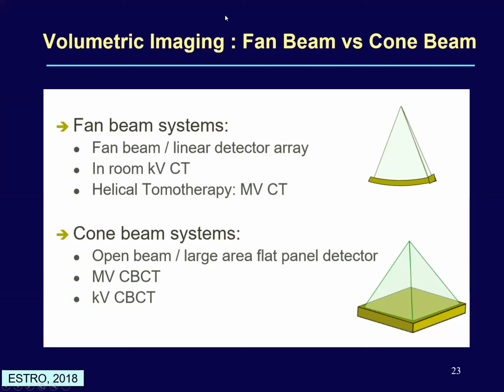Now coming to volumetric imaging, fan beam versus cone beam. What is fan beam? A single KV source with a linear array detector on the O-ring, and the source rotates in a helical fashion, and you can have a fan beam CT, which is conventionally available in all diagnostic CT scanners. In the same way, in helical tomotherapy, they have an MV source and a detector in an O-ring structure, and produce an MV fan beam CT. In the linear accelerator, you can have a wide, large area beam, and so we needed a large panel amorphous silicon detector, like 40 by 40 centimeters. And you can use the same thing for producing an MVCBCT or a KVCBCT.